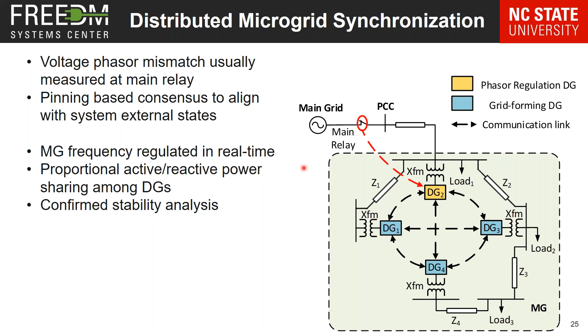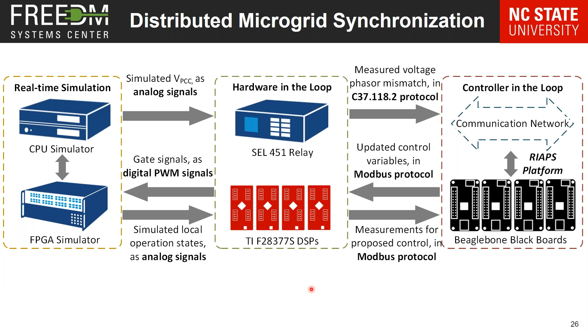In the interest of time, I'll breeze through this. Basically, you simulate the grid, you simulate your high frequency power electronics, and send signals to standard hardware you'd find in a substation. That goes back to the communications network where you have all your little BeagleBones representing the RIAPS nodes. Communicate however you need to, whatever protocol—Modbus one way, or MQTT another. This one is the C37 protocol for phasor measurement units, to be able to match that voltage and frequency so you can resynchronize with the main grid.